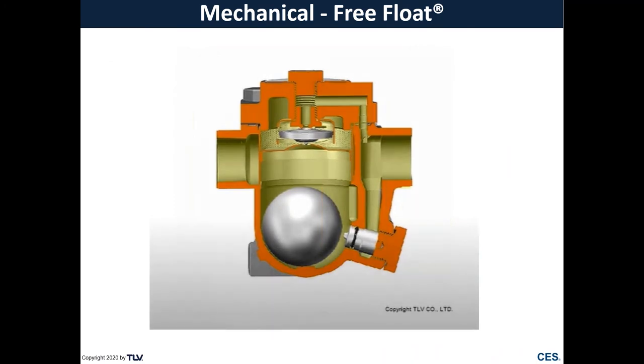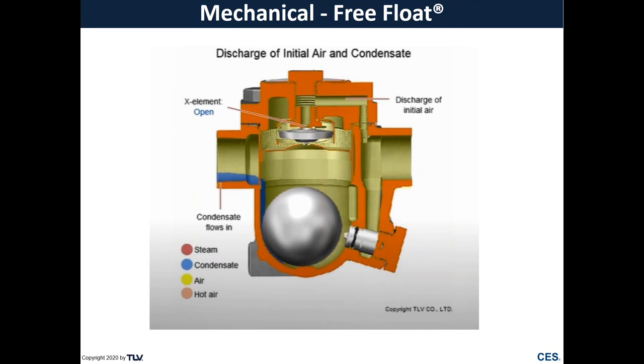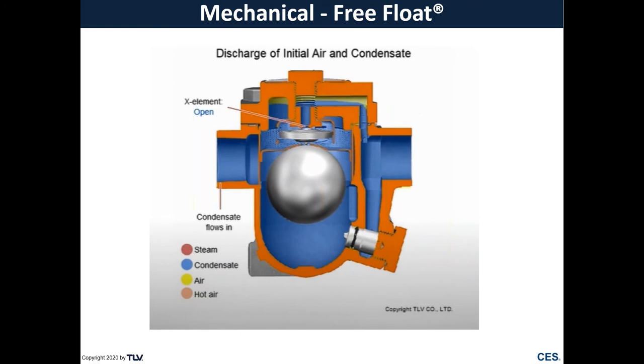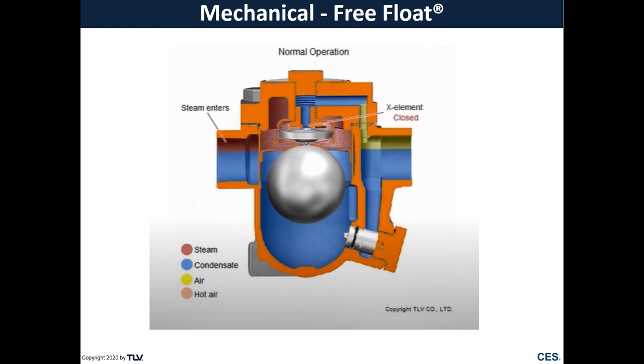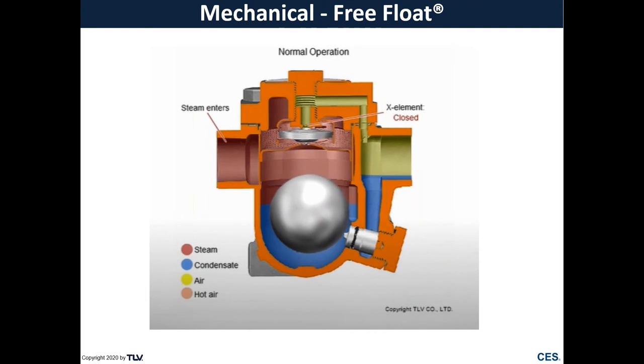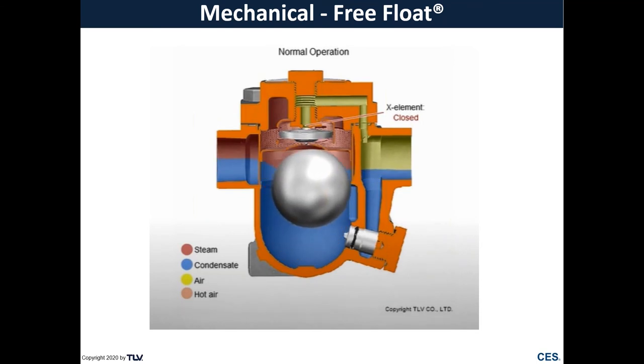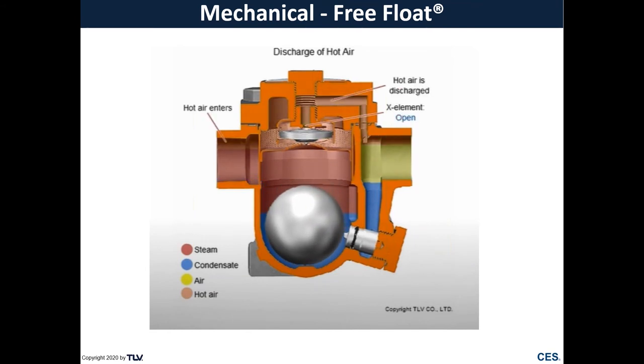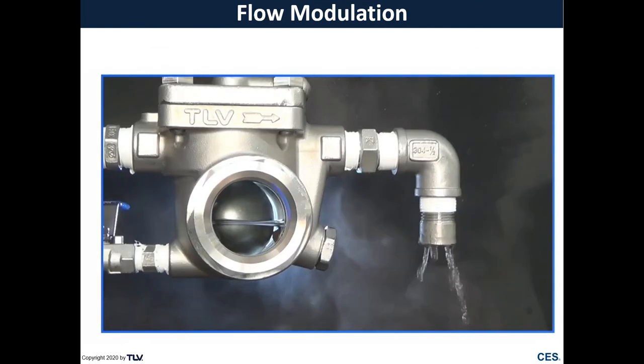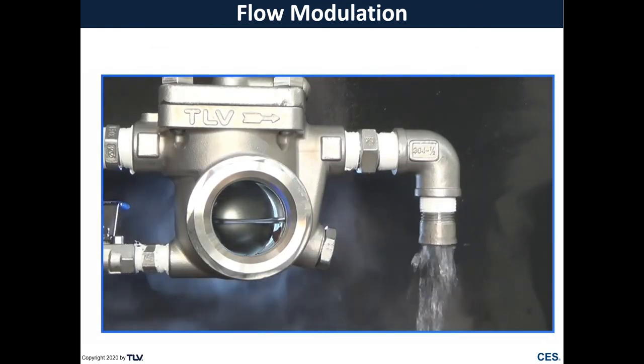The next trap I'm going to cover is TLV's free float. So you'll notice there's a float in the bottom as well as the X element that I discussed earlier. So we discussed how the X element operates. It's going to be wide open during air and cold condensate. So this will help out with the startup of your system. As steam enters, the X element's going to close, and now our main operating function is that float and orifice at the lower side of the trap. As condensate begins to enter the trap, the float becomes buoyant and just kind of modulates around that orifice, allowing condensate to discharge downstream. So let's take a look at what that looks like with an actual video.